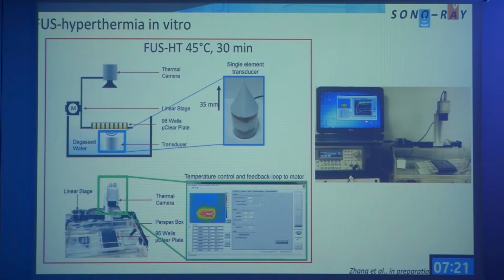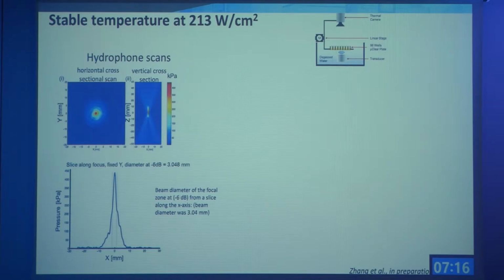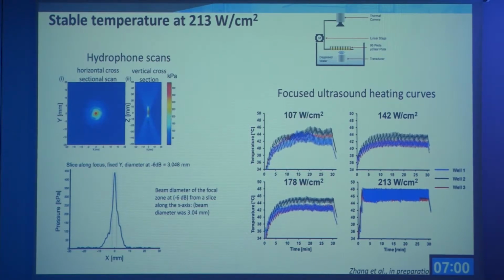Then you can see the plate is moving during the treatment. On the left side, you see the acoustic field characterized by a hydrophone. We can see the size of the focus point is the same as one well in the 96-well plate. And to get stable hyperthermia, we tried different acoustic intensities, and we found that at 213 watts per square centimeter, we can get stable hyperthermia at a mean temperature of 45 degrees within 2 minutes.